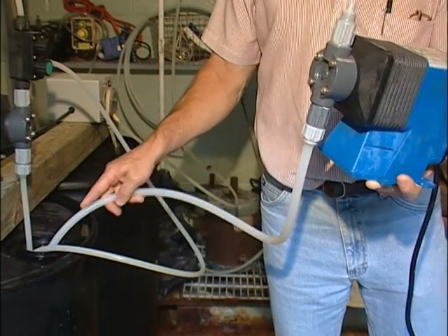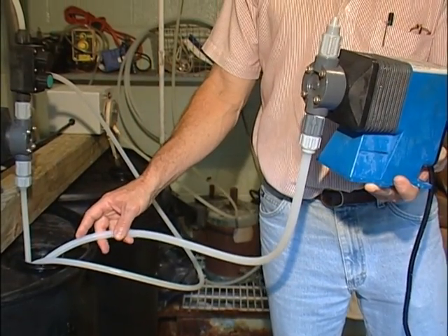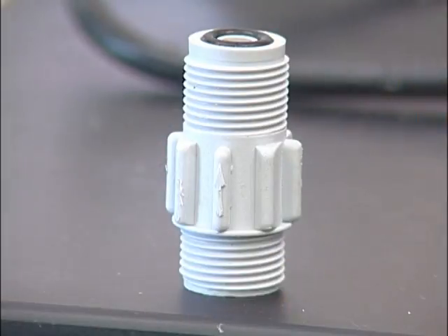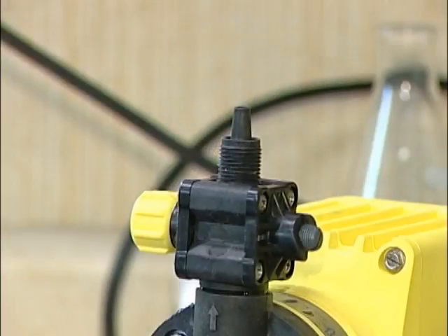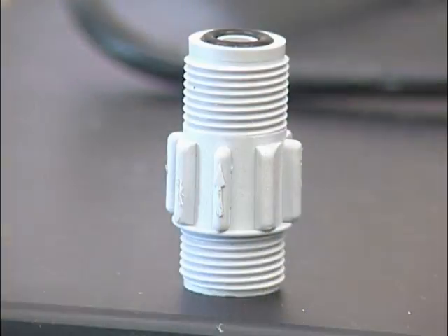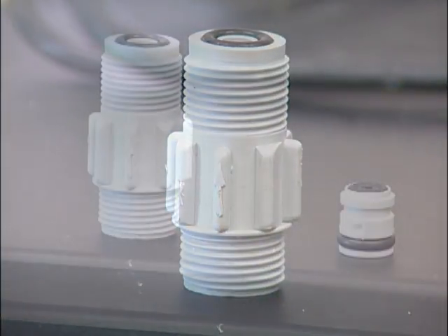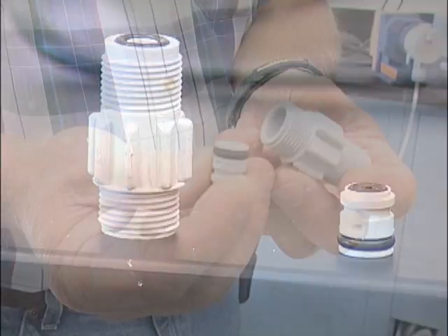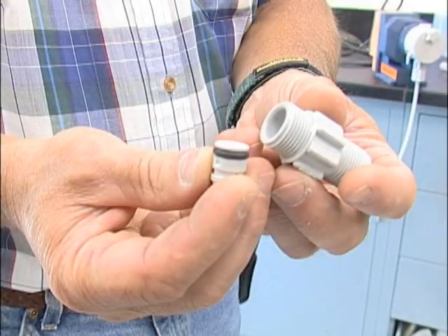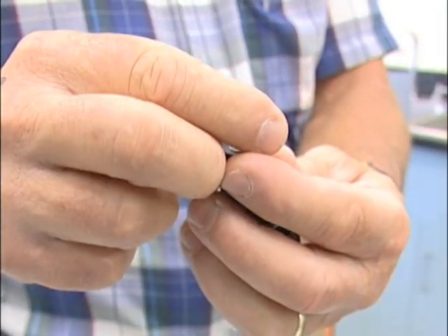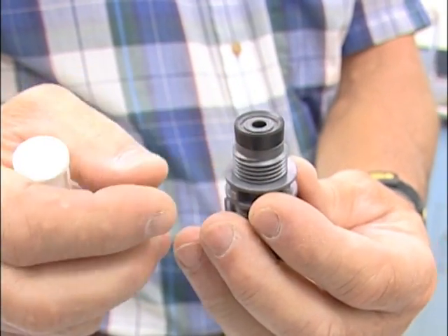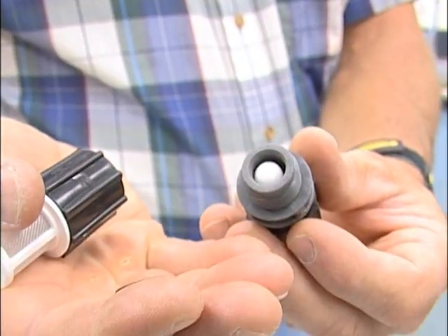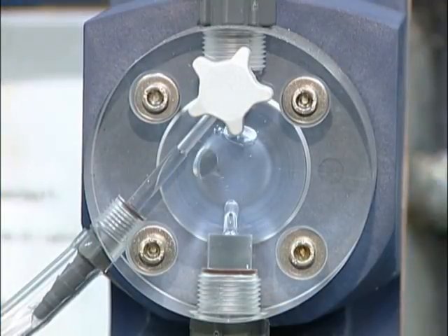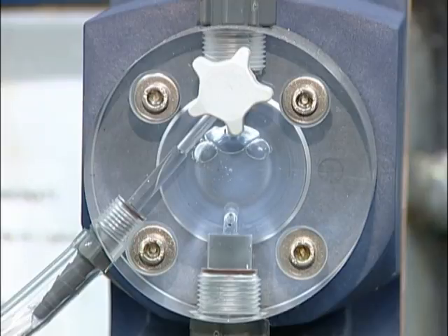Other pieces of equipment that are essential to the operation of chemical feed pumps are check valves, foot valves, and four-way valves. Check valves prevent the backflow of water out of the supply side of the pump so that the pump does not lose prime between operations. They are frequently nothing more than a porcelain ball that rests against a plastic housing like this. This prevents leakage from the feed line, which would result in a loss of prime to the pump if it occurred.